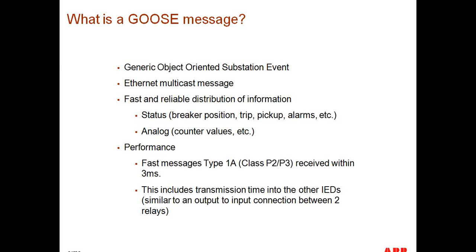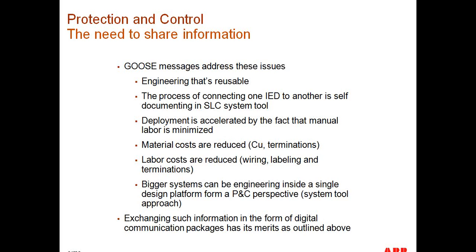And by listening to that traffic, they'll be subscribing to the analog information from those current transformers and voltage transformers. In the current 9-2 LE implementation guidelines, the makeup of that communication package is 4 voltages and 4 currents. So that would be phases A, B, and C, and your neutral for current, and then phases A, B, and C, and neutral for your voltages. Okay, let's go ahead and continue.